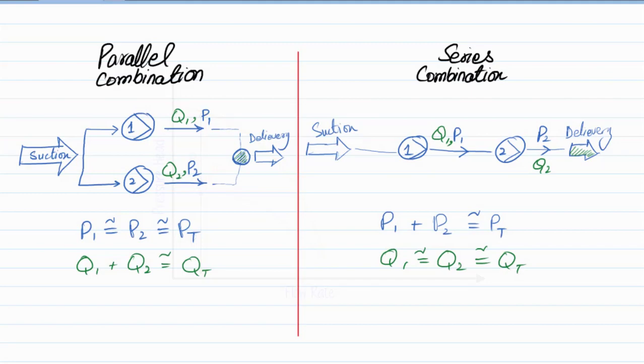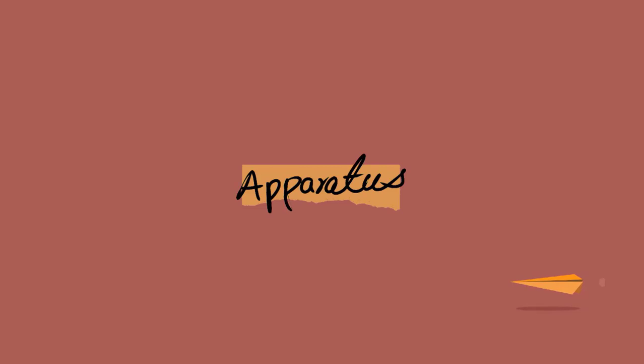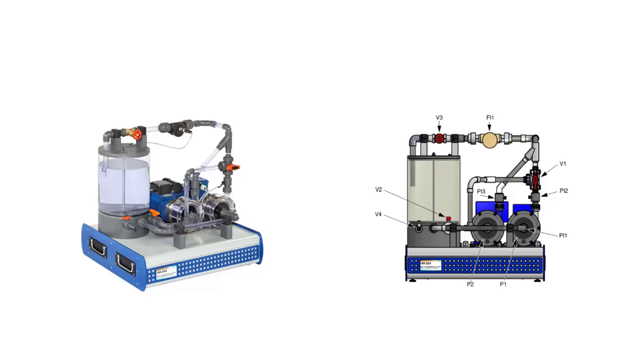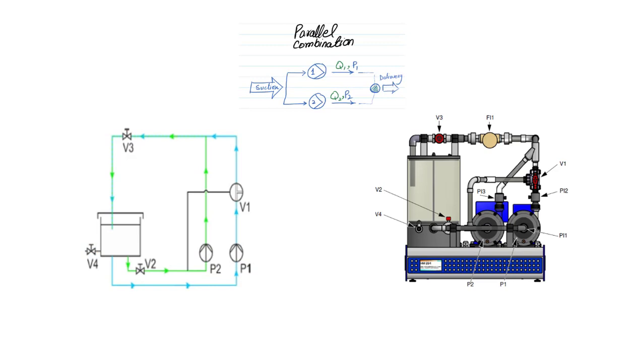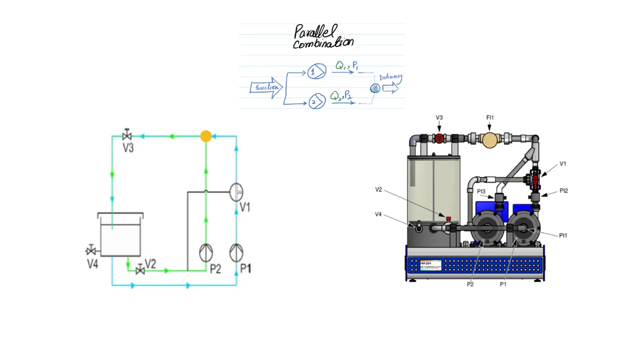Because we know in series, flow rate doesn't increase but pressure does. The apparatus used in today's experiment is the same as we used last time. But this time we will operate both pumps and make their different combinations. Both pumps in this apparatus are connected to motors. Pump 1 is connected to VFD, pump 2 runs at constant RPM. First, let's discuss parallel combination. We've studied that in parallel combination, suction point is same, so for both the suction point is the tank. Water will pass from these pumps and there pressure will be increased. Then both streams will meet at this point and from there through valve 3.